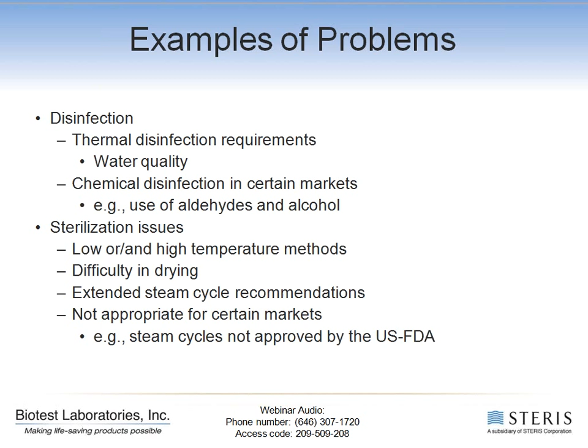Also, there are many types of requirements for certain markets, just like I've highlighted for chemical disinfection, where you may have steam sterilization cycles that are just preferred in certain countries or approved in certain countries, like by the US FDA in the US, as well as internationally, where you can have specific requirements. For example, in France, the use of a sterilization cycle at 134 degrees Celsius for 18 minutes is quite common.